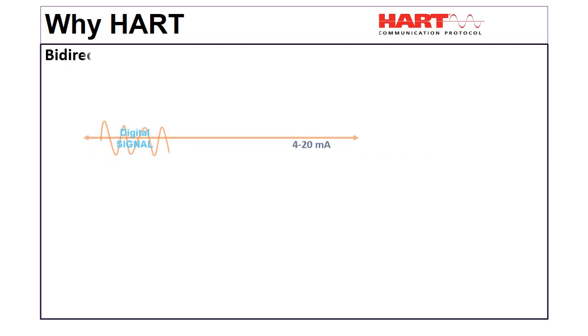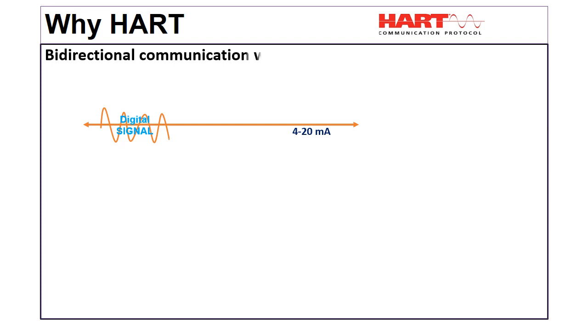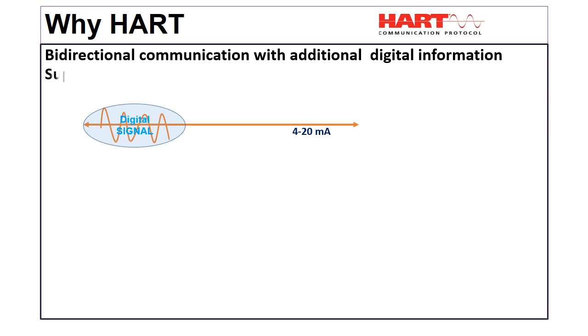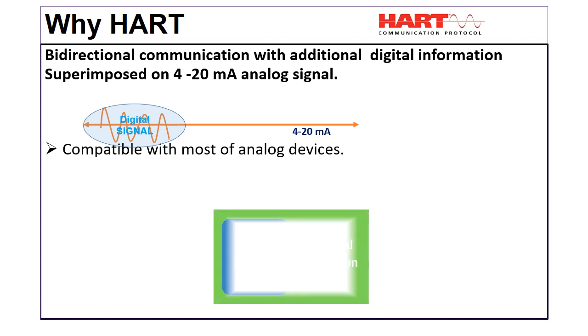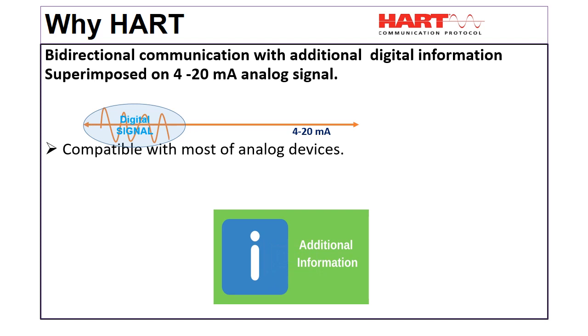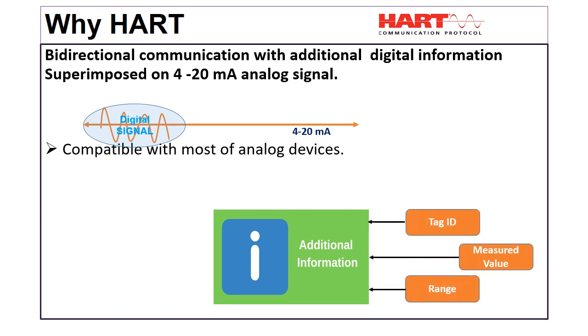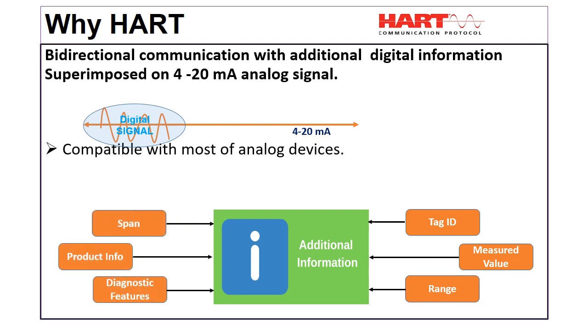HART is a bi-directional communication protocol in which additional information can be transmitted by superimposing a digital signal on the existing 4 to 20 milliampere analog signal. HART is compatible with most analog devices. HART provides additional information such as device tag ID, measured value, range, span, product information, and diagnostic features.